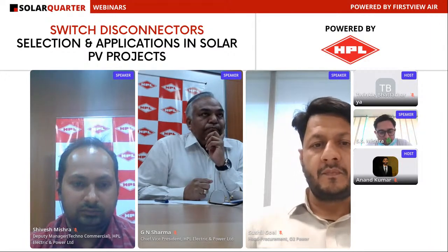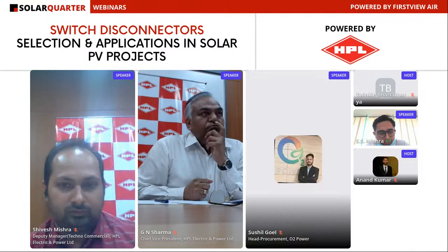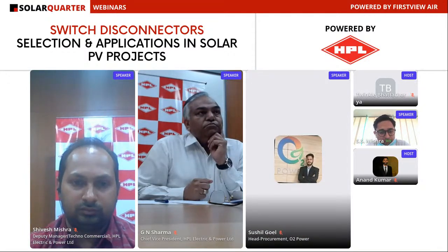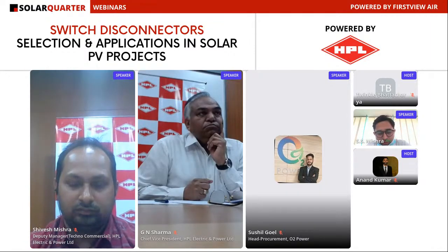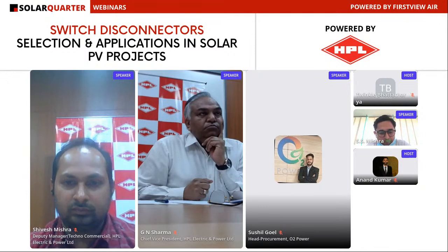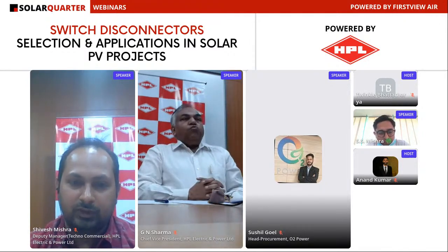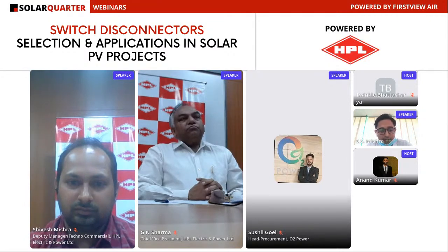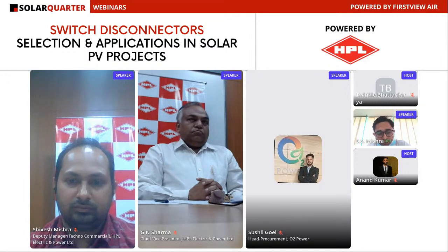Previously we were getting a 330 watt peak module, and the DC sizing was completely different. Now we are getting a 540 watt peak module, and with the recently awarded project, we have completely designed it on a bifacial with tracker. So the DC side capacity is increasing, and as Mishra sir mentioned in his initial remarks, we want the industry to come up with a bigger string combiner box size - maybe increase from 400 amps to 500 or 630. Of course, it should be backed by proper testing and be a reliable product, because the scope left for cost optimization is very, very less now after the modules. There are not many options left for a developer, EPC, or IPP to optimize on cost.